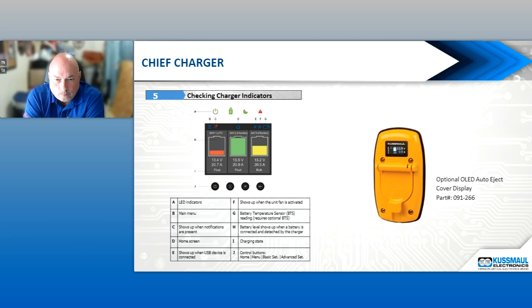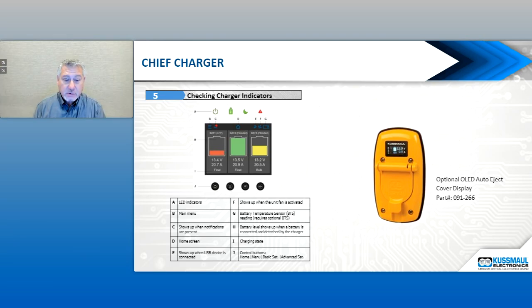And if you are replacing an older style charger with the new Chief charger and it has an old bar graph display, you will need to upgrade the display. This has the same bolt pattern as the bar graph display - I'm holding up the screen if you can't see it. It does have a separate, I say display, it's actually a remote control panel. It's a touch screen as well. You can actually do the changes to the charger from that remote control panel, and you can also set a password so you don't have to worry about people changing your settings.